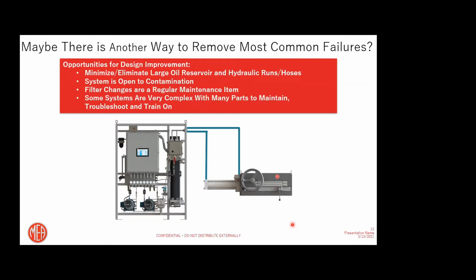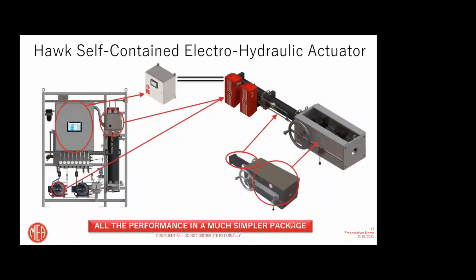So is there another way of making it more simple? We thought about this for years. And 5 years ago, MEA developed a different type of technology, called MEA Hawk, a self-contained electrohydraulic actuator. To develop this technology, we rethought the whole way we did electrohydraulics for years. As we talked about, we had a constantly running motor pump assembly, which took the hydraulic fluid from a reservoir, then charged the accumulator, and then you used this hydraulic fluid to run your cylinder. And you had to constantly run your motor pump assembly to charge the accumulator.